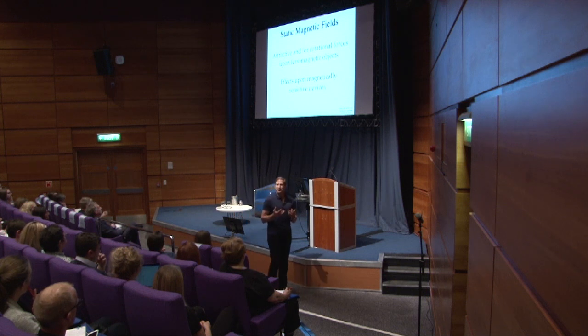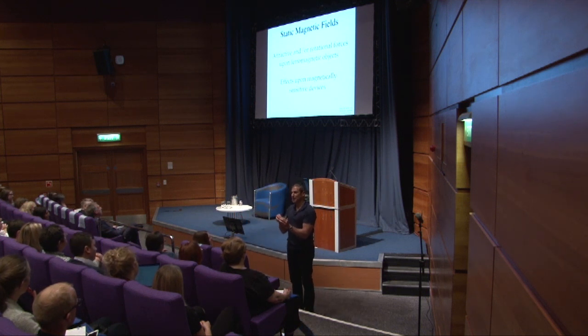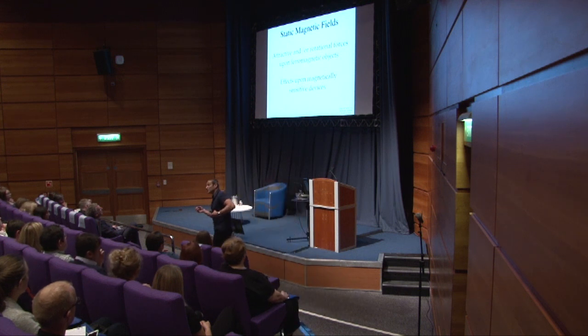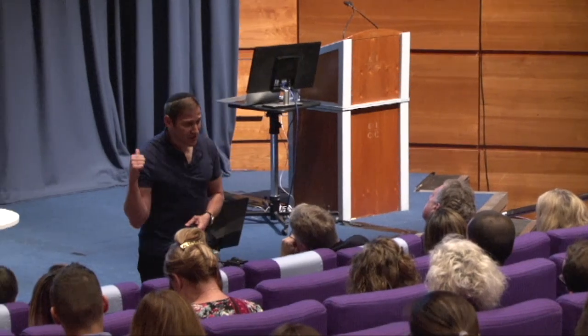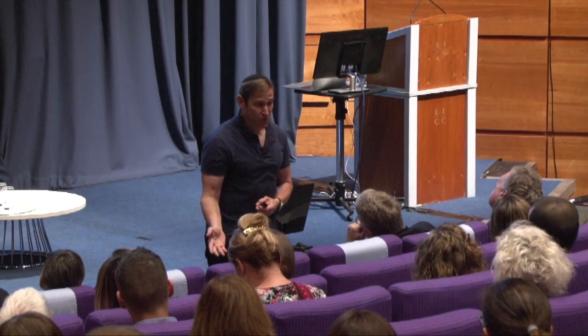People use examples like pacemakers, defibrillators, but it could be multiple devices. The adequate function of an insulin pump is an integral part of the safety question: can I safely expose them? You don't want that insulin pump suddenly malfunctioning and delivering the entire reservoir of insulin to the patient as a result of the MR scanner, leaving them comatose or dead.